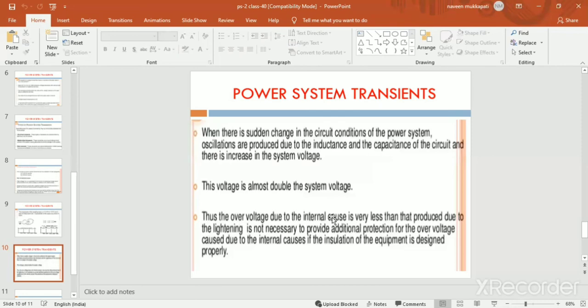Thus the over-voltage due to internal causes is very less, producing fewer over-voltages. However, for over-voltages produced due to lightning, it is necessary to provide additional protection, even if the insulation of the equipment is designed properly. Due to lightning strokes obtained near overhead transmission lines, the internal insulation of the equipment gets somewhat damaged.